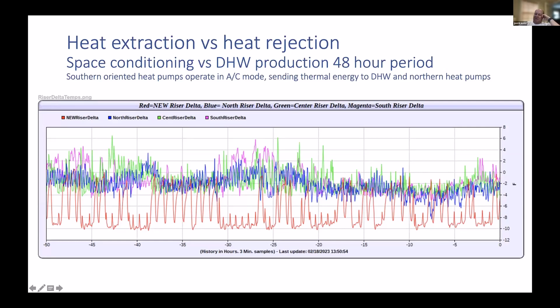But you can see how there's a lot of energy sent around the building. It all goes through the loop field, but this water is mixed before it goes in and out. So there's a lot of exchange just between the heat pumps themselves. Not a single BTU or kW is wasted. It all finds its way back to other sides of the building which are operating in heating mode.